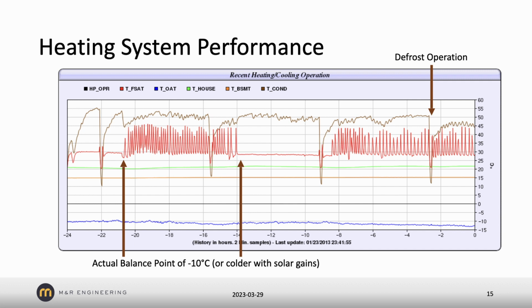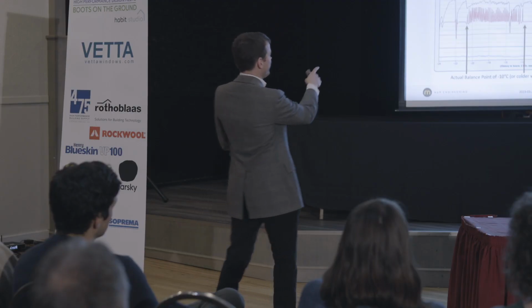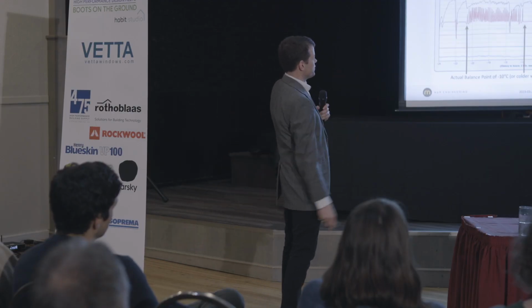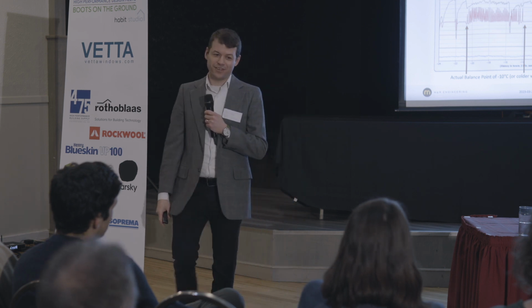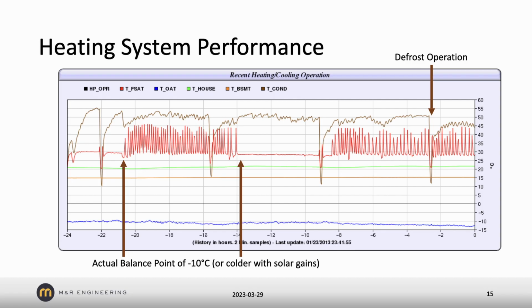If you might remember on the previous slide, my balance point temperature is what the dashed vertical line is. It was designed for about 30 degrees Fahrenheit, or about -1 Celsius, for the balance point. In reality, the supplemental heat didn't kick in until about -10 or -11 Celsius. But that was overnight. The sun comes up and comes out in the daytime, and you can see there was like a 6 or 7 hour stretch where it didn't have any supplemental heat down at -10 or -11. You can also see there's defrost kicking in every 6 hours. It doesn't kick in very often, so it doesn't really have a big impact at those temperatures.